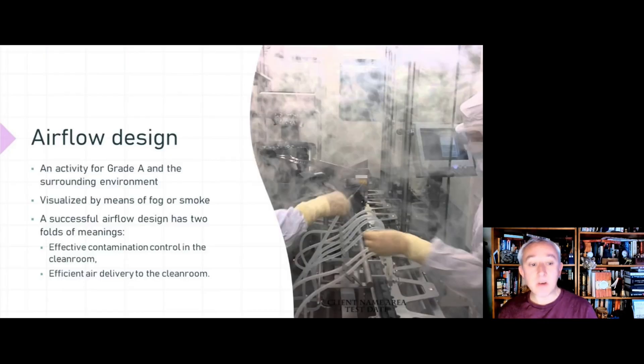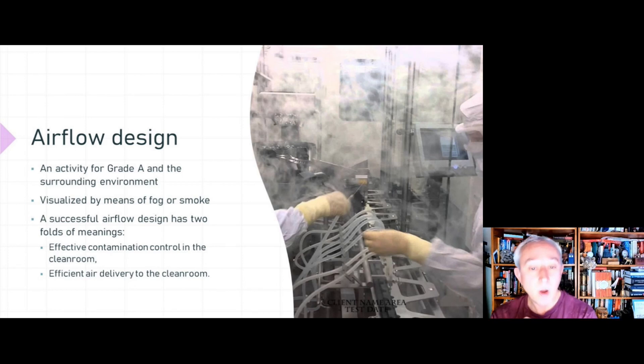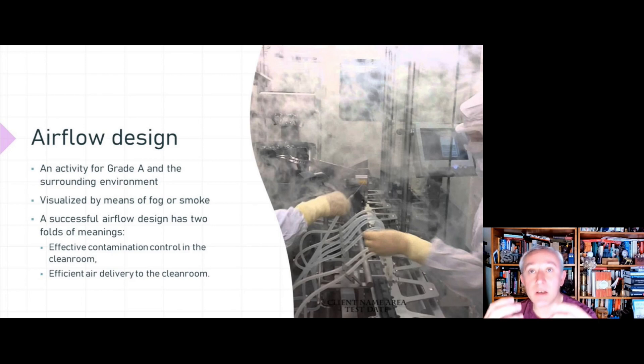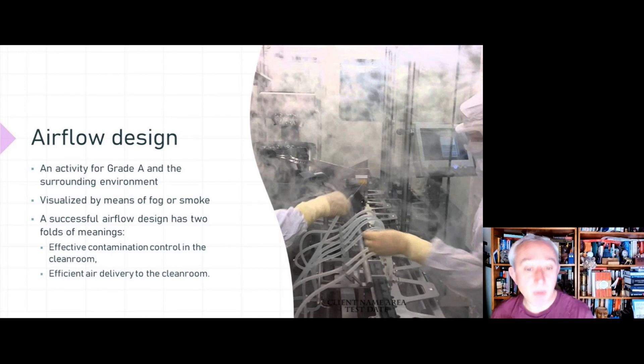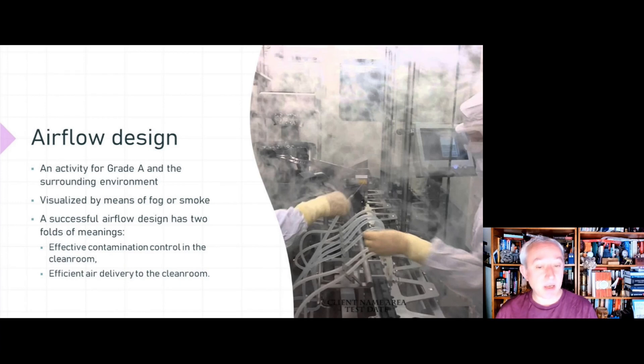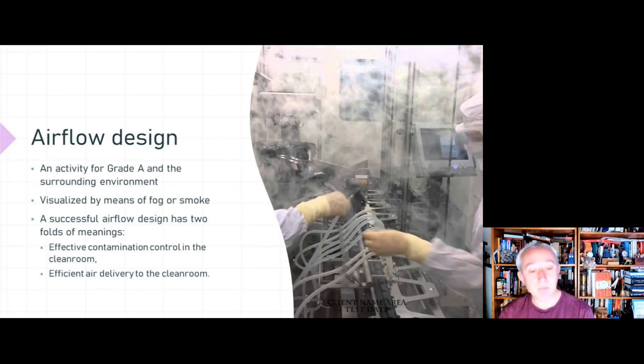So first of all, why airflow visualization studies? It's an activity that helps us to assess airflow design, looking at the Grade A or ISO class 5 environment and also the surrounding environment. We visualize this by means of fogging or the generation of smoke. A successful airflow design has two key meanings: effective contamination control in the clean room, and efficient air delivery to the clean room.